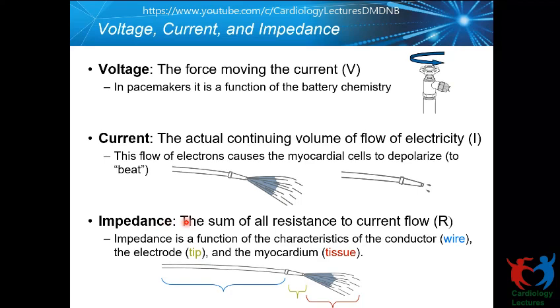The sum of these components is the total impedance. By design, companies make the lead conductor a low impedance conductor so that all the electrons that start from the pacemaker battery are able to reach the tip with the least resistance. That means if I give 2.5 volts from the battery, then at the lead tip I want to deliver close to 2.5 volts. But if the impedance is higher at the conductor, then a lot of it may be wasted as heat, which we do not want. So by design, the conductor electrode will usually have the least resistance.